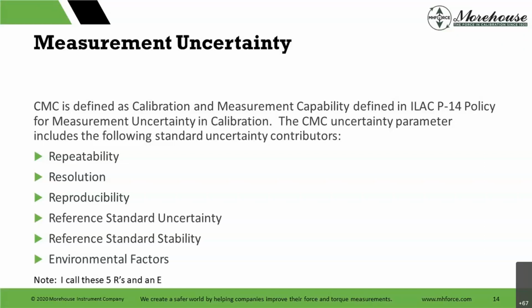It includes repeatability. Remember, we were just looking at a slide with precision. It includes the resolution of the device. Lots of people now want to take this resolution out. Oh, we don't need it. If our standard deviation shows something with repeatability, we don't need resolution. ILAC P14 addresses this very, very well in saying, hey, if you have really, really good precise instruments that are showing 0 error or 0 deviation or spread, you will take that resolution into account.